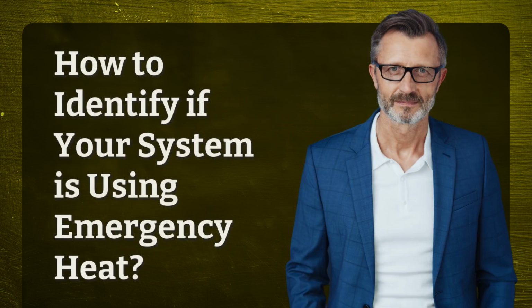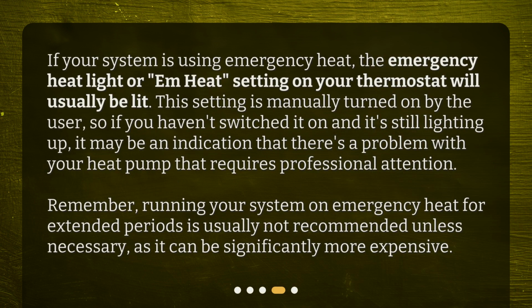How to identify if your system is using emergency heat? If your system is using emergency heat, the emergency heat light or Em Heat setting on your thermostat will usually be lit. This setting is manually turned on by the user, so if you haven't switched it on and it's still lighting up, it may be an indication that there's a problem with your heat pump that requires professional attention. Remember, running your system on emergency heat for extended periods is usually not recommended unless necessary, as it can be significantly more expensive.